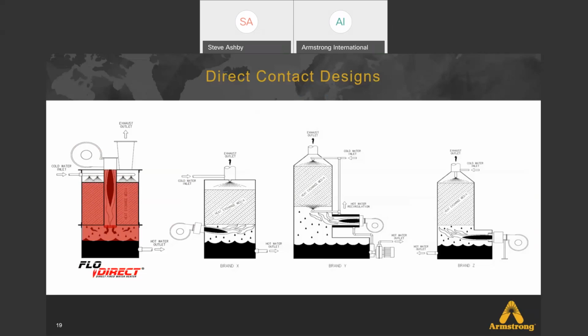The other heaters here as well, with that burner sitting on the side and firing horizontally across, that also, as you can imagine, can cause an issue on the opposite wall. And that opposite wall gets very hot, and over time of continual operation, that becomes a maintenance issue, as you'll get that sidewall failure. So again, they're just to show you the differences. Both are generating hot water. Both are generating hot water efficiently. Maintenance issues definitely favor the vertical design as far as minimal maintenance.